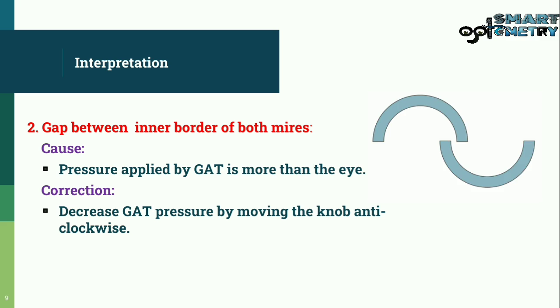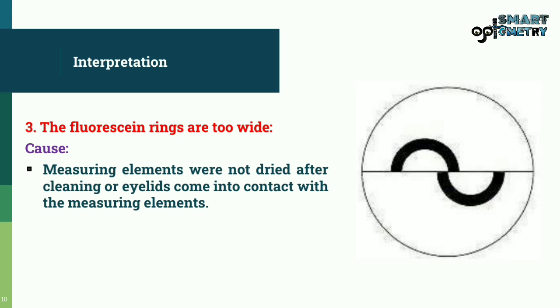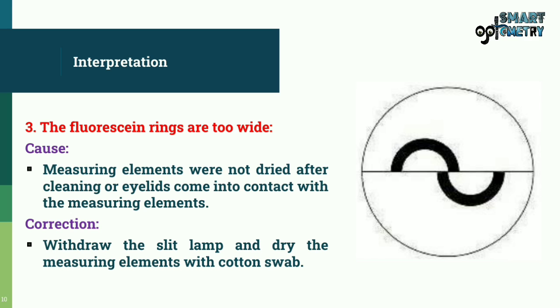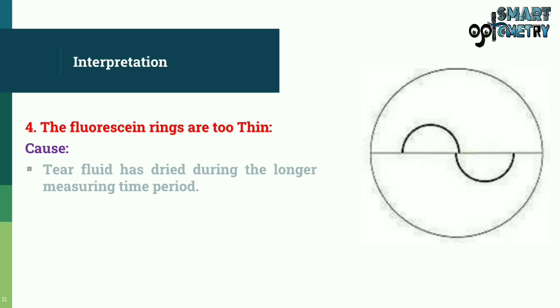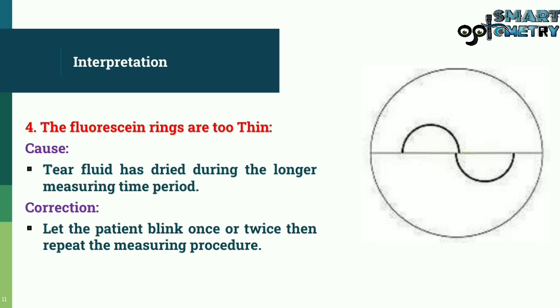Fluorescent rings that are too wide indicate that the measuring elements were not dried after cleaning, or eyelids came into contact with the measuring elements. Correct by withdrawing the slit lamp and drying the measuring elements with a cotton swab. Fluorescent rings that are too thin indicate the tear fluid dried during a longer measuring time — correct by letting the patient blink once or twice, then repeat the procedure.